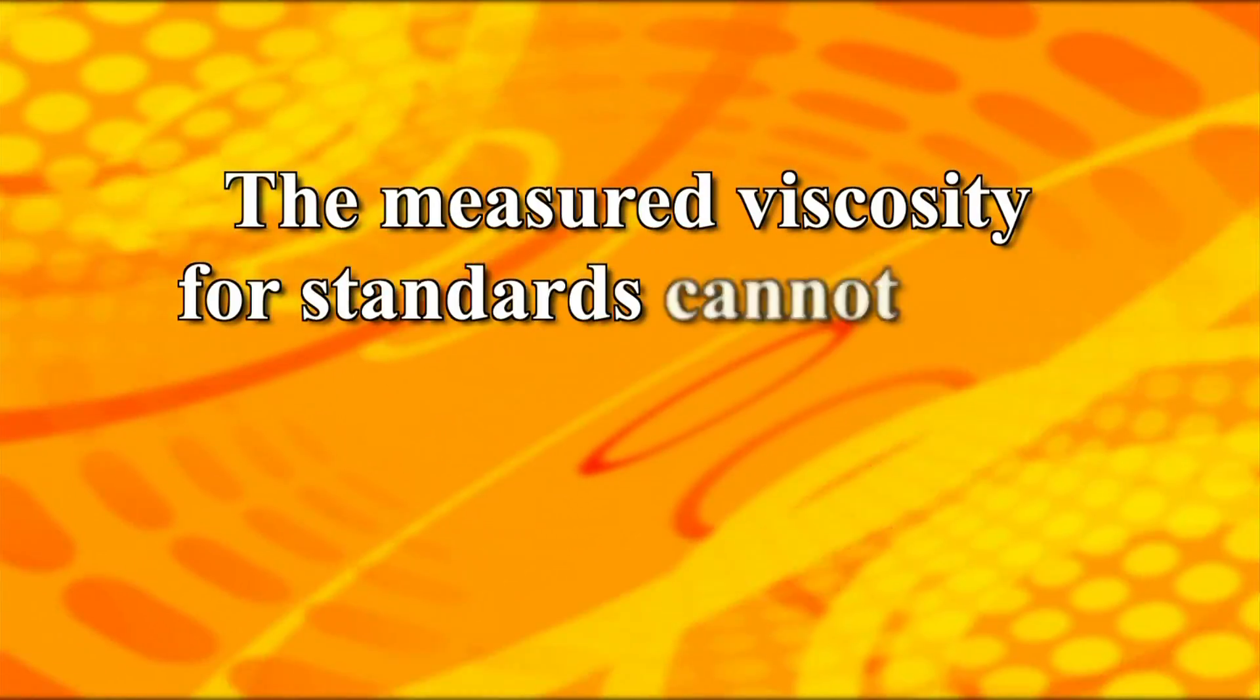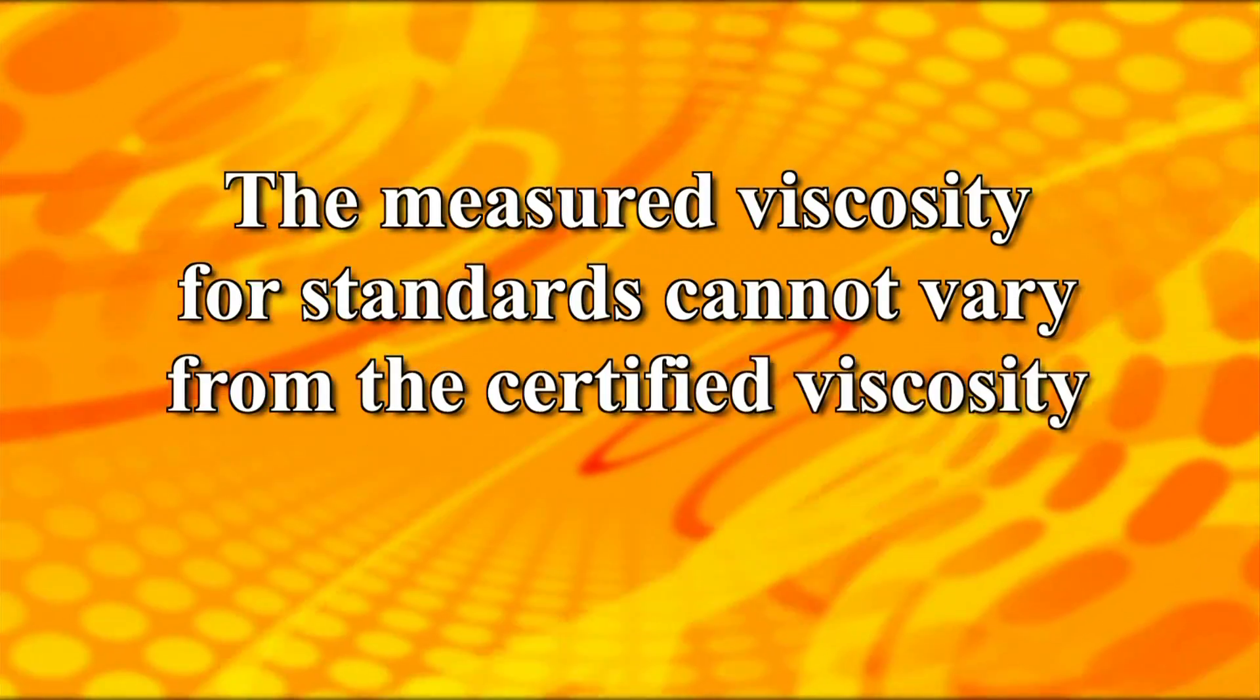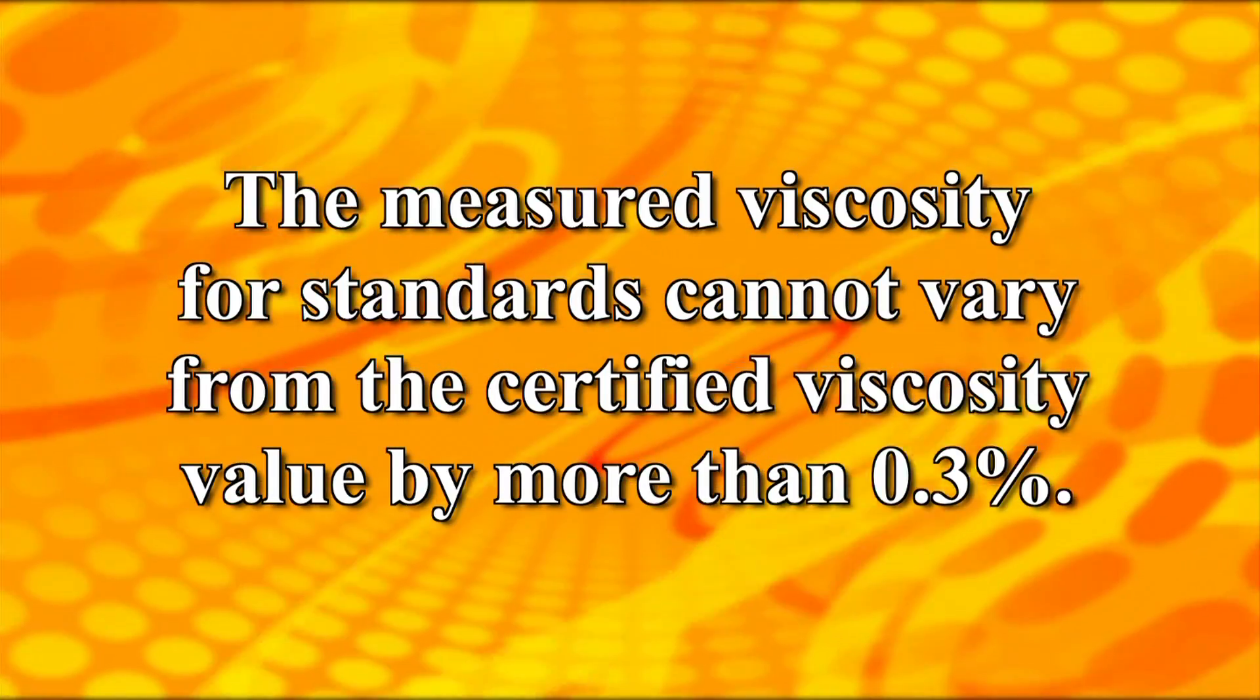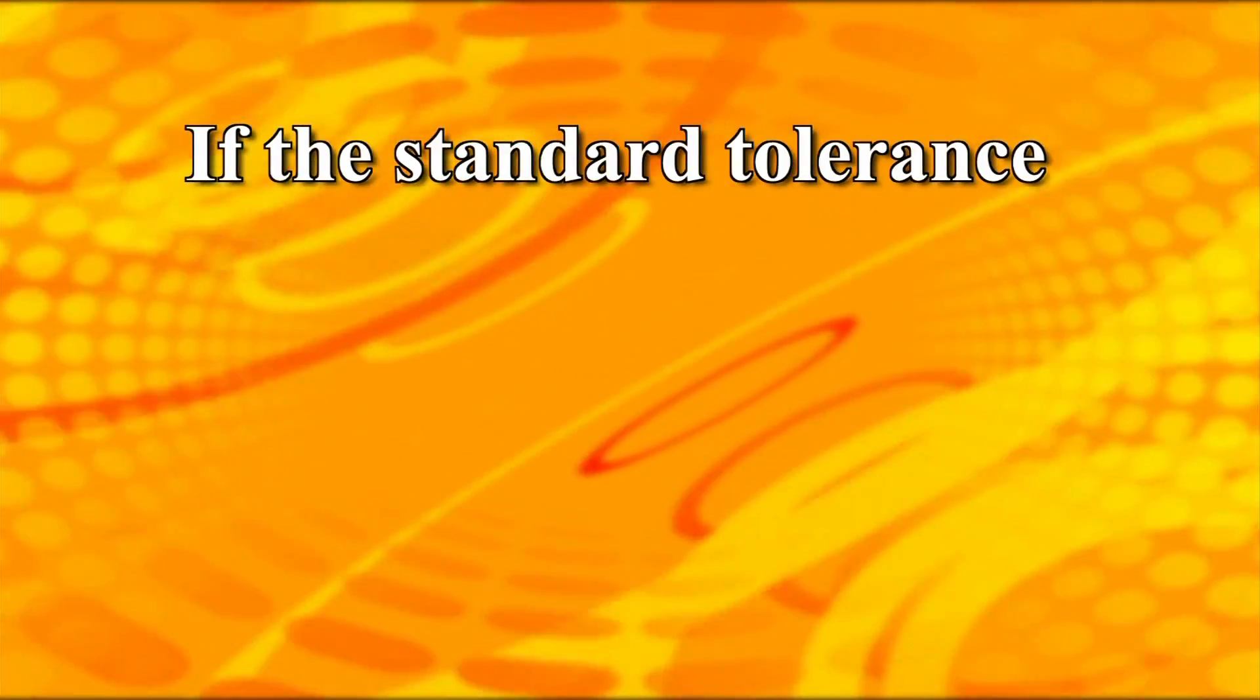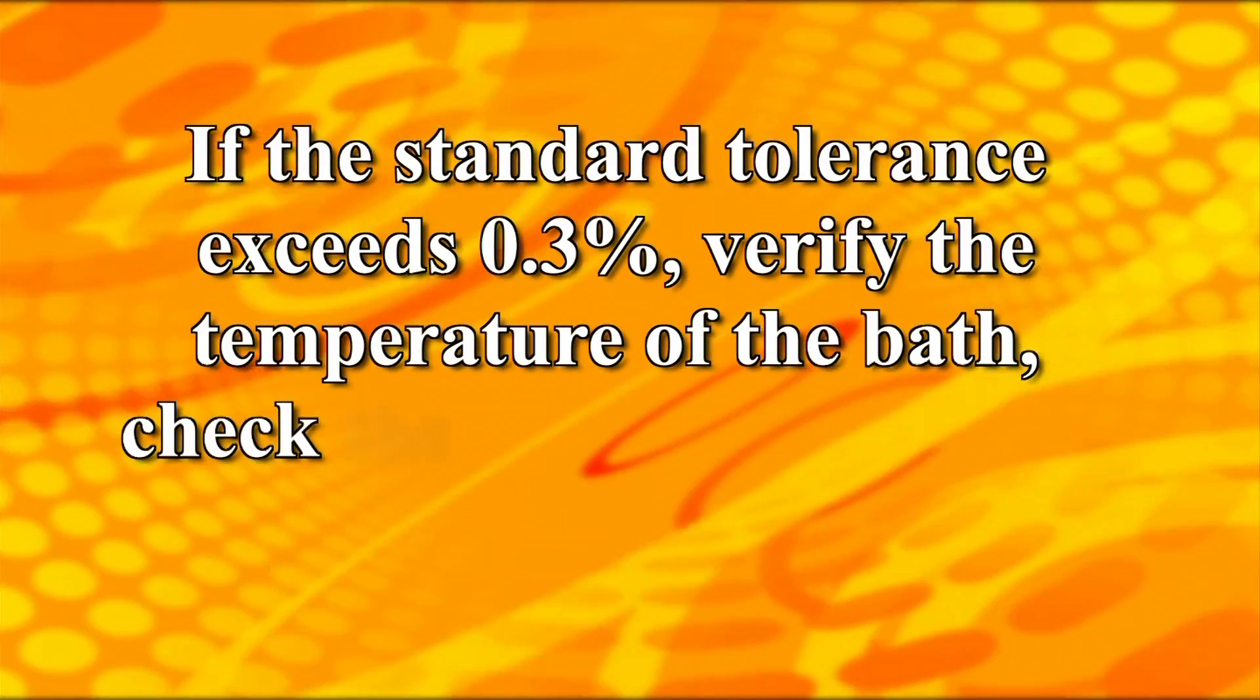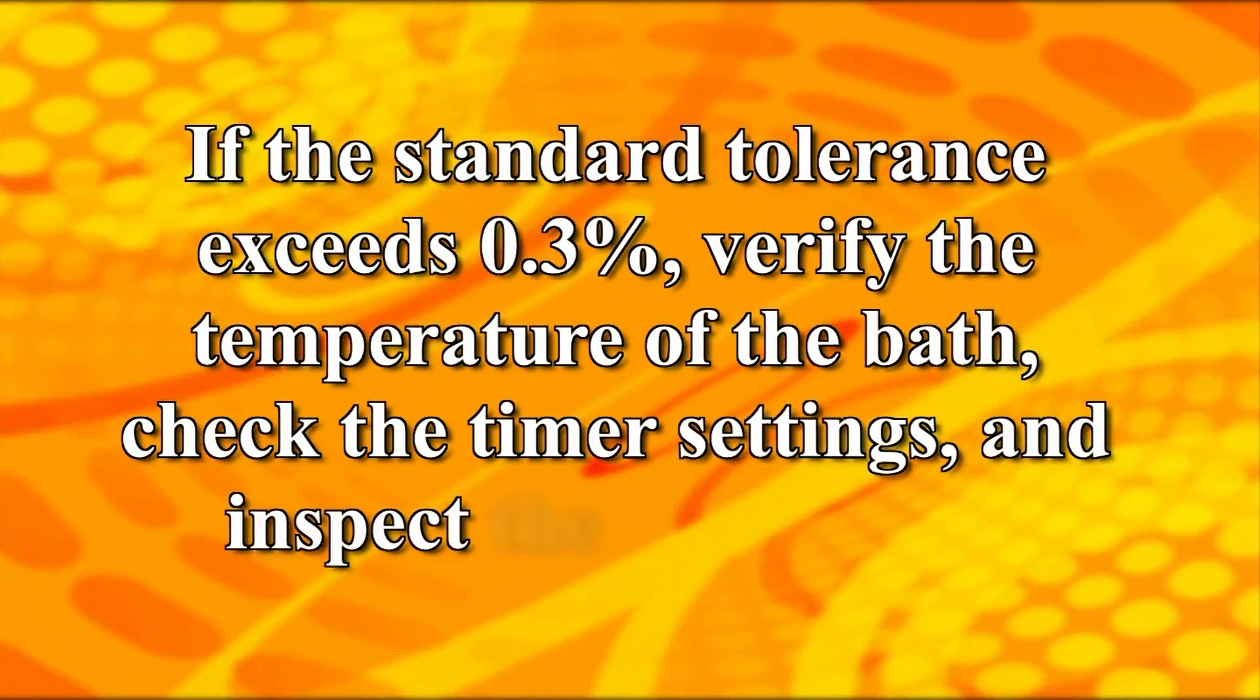The measured viscosity for standards cannot vary from the certified viscosity value by more than 0.3%. This is the standard tolerance. If the standard tolerance exceeds 0.3%, verify the temperature of the bath, check the timer settings, and inspect the viscometer.